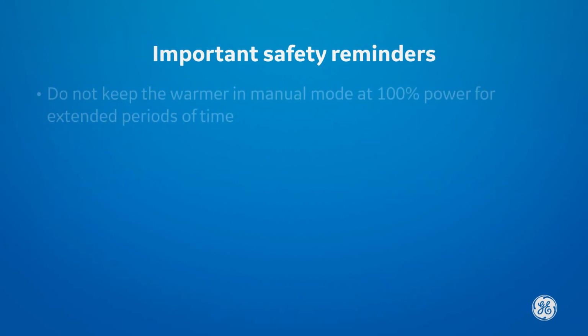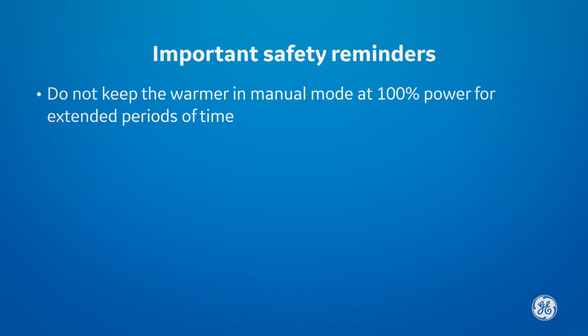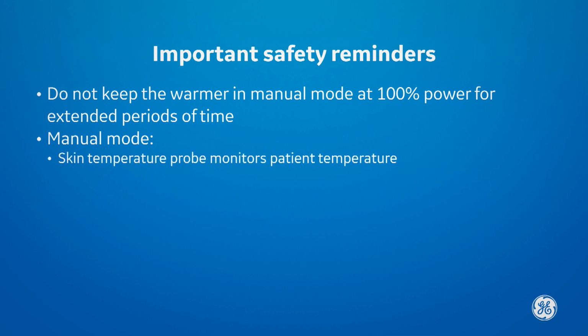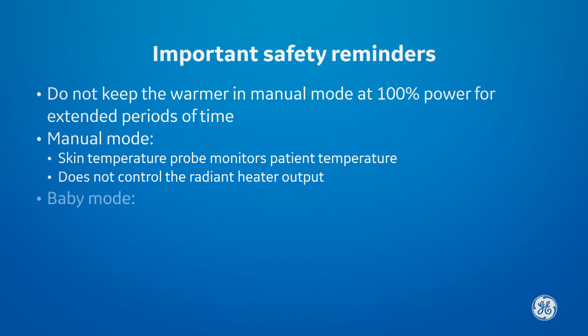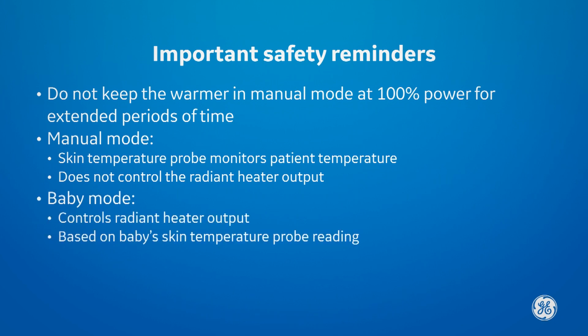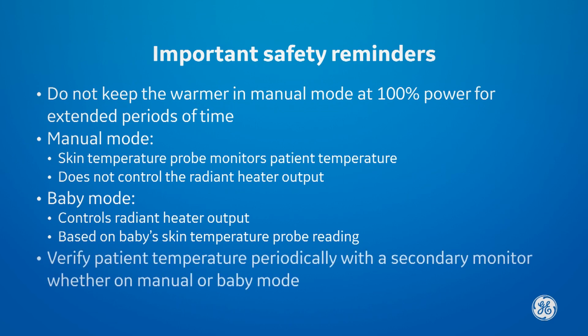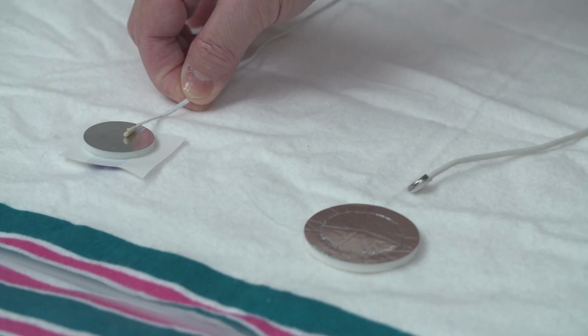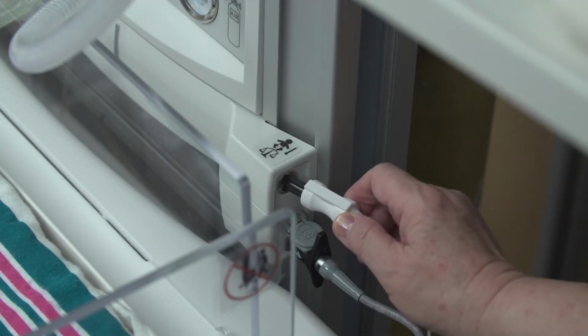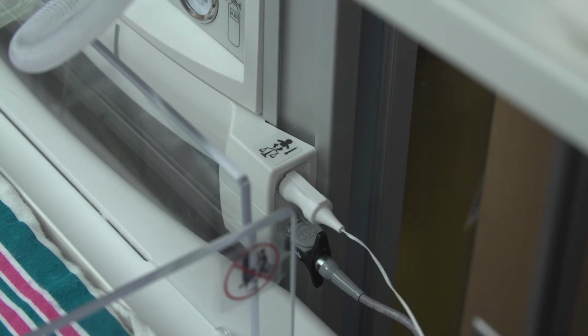Once the patient is admitted, do not keep the warmer in manual mode at 100% power for extended periods of time. You can use manual mode with the temperature probe to monitor the patient's temperature, but remember, it will not control the radiant heater output in manual mode. You must be in baby mode to have the radiant heater output controlled by the baby's skin temperature probe reading. It is important to verify the patient's temperature periodically with a secondary monitor, such as a thermometer. Using a skin temperature probe is recommended. Ensure it's connected to the skin temperature probe jack of your bed.